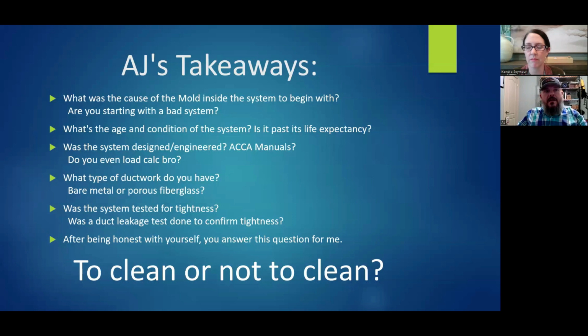Was the system designed and engineered properly? Were the ACCA Manuals followed? Is the system too large for the house? Does it have the latent capacity to handle the moisture load of the house? Is the ductwork sized properly to deliver the capacity where it's needed? Does the system have porous open fiberglass insulation that would need to be removed? If it does, in my opinion, it's not worth cleaning. Was the tightness and performance tested and confirmed? Not doing these things could be what's causing the mold in the first place.